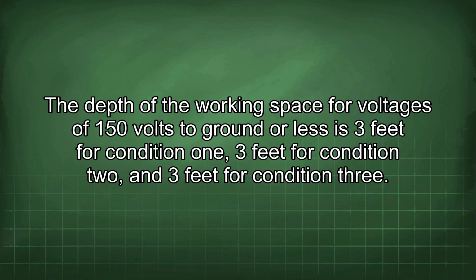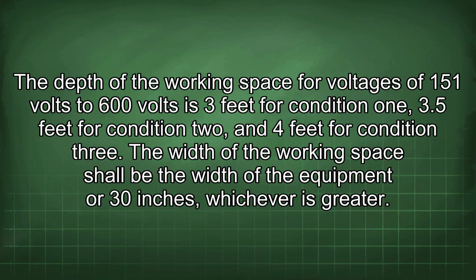The depth of the working space for voltages of 150 volts to ground or less is 3 feet for condition 1, 3 feet for condition 2, and 3 feet for condition 3. The depth of the working space for voltages of 151 volts to 600 volts is 3 feet for condition 1, 3.5 feet for condition 2, and 4 feet for condition 3. The width of the working space shall be the width of the equipment, or 30 inches, whichever is greater.